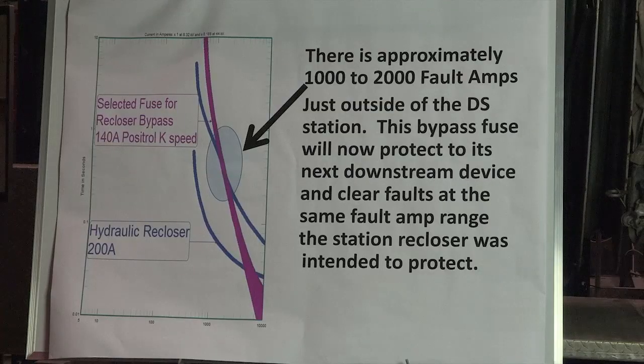This last diagram here is basically showing how we choose a fuse for an MUS installation. So here we have the bypass fuse that's in purple, and the station's reclosers. Outside the station, there's approximately 1,000 to 2,000 fault amps, and we want this high side fuse to protect just the same way as the recloser did.